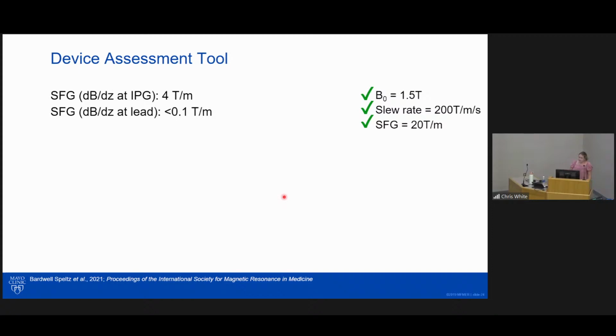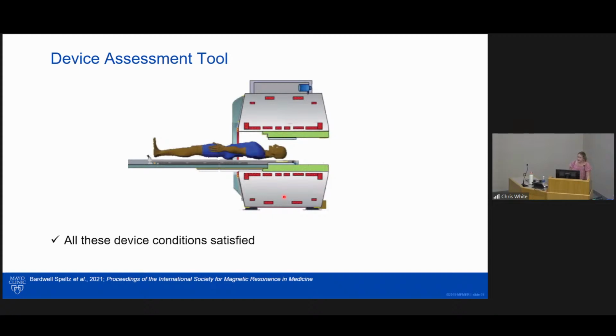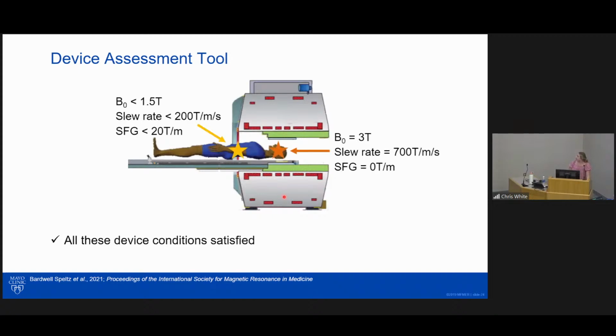So this example demonstrates how the device assessment tool can be used to help ensure the conditions of MR conditional implanted devices could be satisfied at the location of the device, even if they are exceeded at the location of the anatomy being scanned. Here we have our same image as before, and now we can appreciate the reduced electromagnetic fields between those 2 star locations. Here we have the reduced B0, slew rate, and spatial field gradient.